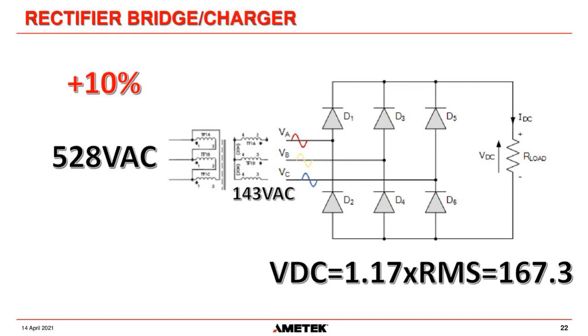Because what is the main purpose of the charger? This actually confuses a lot of people. They think it's to supply the DC loads, to keep your switchgear trip and closing supplies on. That's not the main reason for the charger. The main reason for the charger is to charge the batteries. That's the main reason the charger is there. So the batteries are always charged, just in case you have a power failure, then the batteries will continue to feed DC to your DC critical loads.